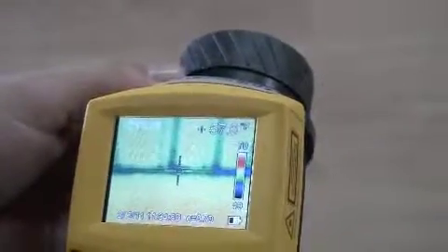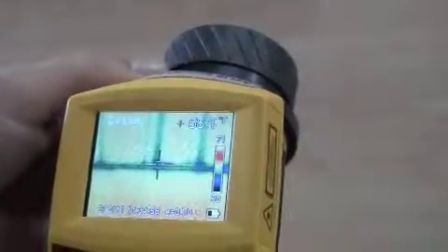We also can see major thermal bridging and air loss down at the bottom plate, and that typically is due to no sill seal or no gluing of their bottom plate to the slab. So we're losing major energy at the base of our home.